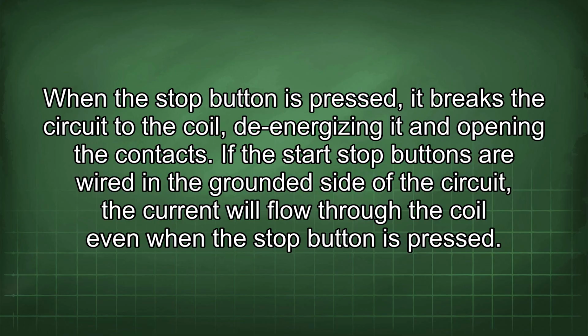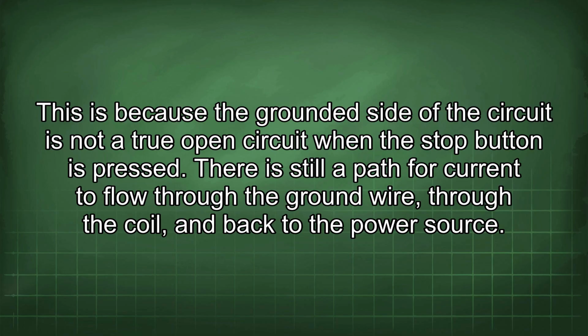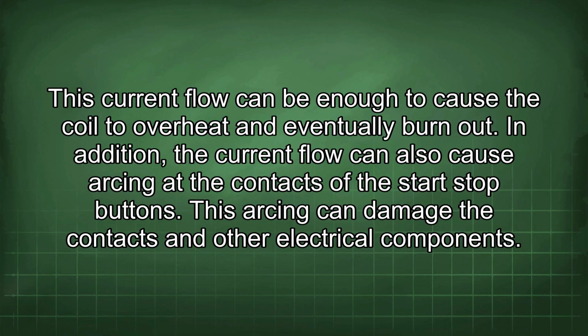If the start-stop buttons are wired in the grounded side of the circuit, the current will flow through the coil even when the stop button is pressed. This is because the grounded side of the circuit is not a true open circuit when the stop button is pressed. There is still a path for current to flow through the ground wire, through the coil, and back to the power source. This current flow can be enough to cause the coil to overheat and eventually burn out.